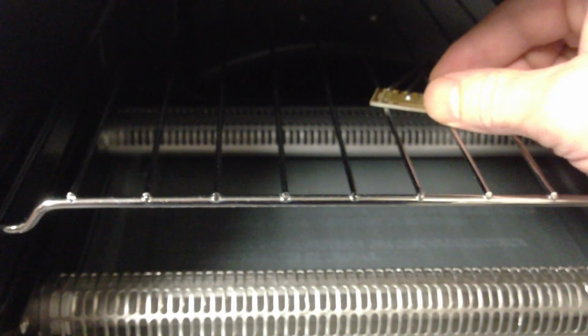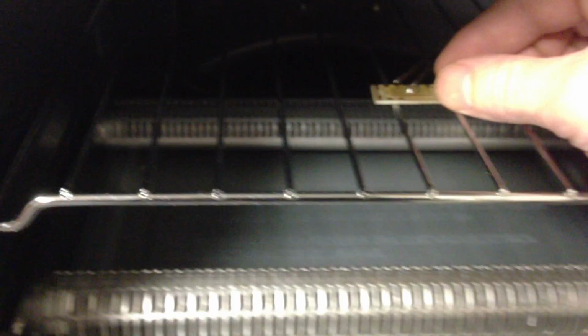This will take about 4 minutes. I hope my resources here don't expend themselves. So anyway, just to let you know what I'm doing inside there, I've got two thermocouples. They're type K. And the idea is if one of them is not working, the other one will still shut it down as a safety measure.